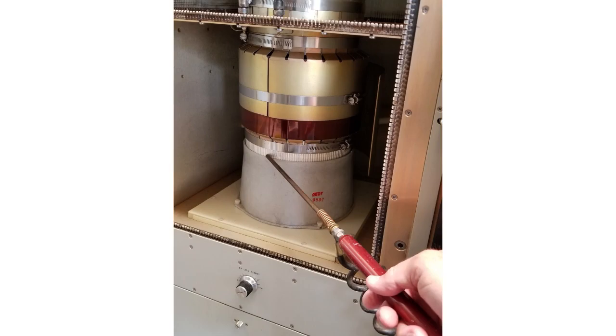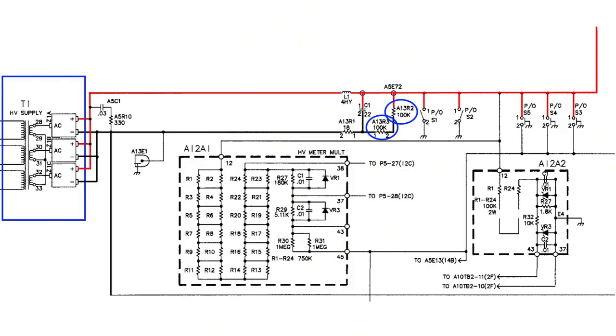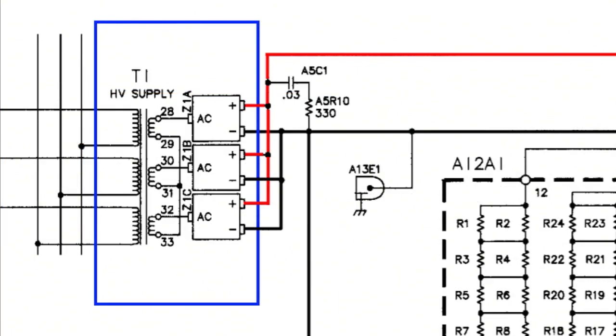Let's flip over to the next photo here and look at a high-voltage power supply. This is scaled down. I cut some of the extra stuff out just so it wouldn't be too much to look at and talk about. If we look over on the left, you see that blue square there? That's around T1. That is a three-phase high-voltage transformer. It takes in three-phase 208 and outputs between 8,000 and 9,000 volts. Then there's three separate rectifiers you can see drawn on the photo there. In reality, there's a lot of diodes in those rectifier stacks.